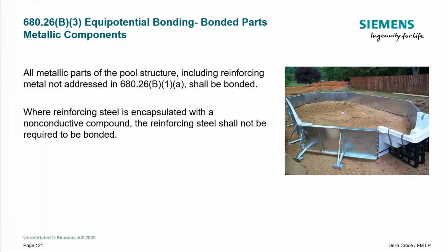And by the way, all this around here does constitute a structural member. This is all structural to the way this pool is built. Not the same as what we would have in rebar and other things like that, right? And I think 680.26(B)(1)(a) is talking about where you might have the structural reinforcing steel, that type of thing, not this.